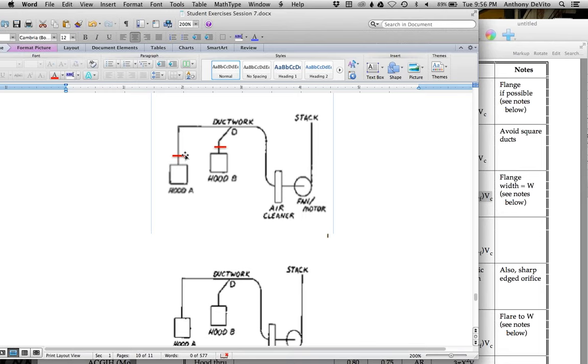They call it a blast gate in these systems. And if it were an air conditioning system like this, it would be a damper, which looks like a butterfly. And you would adjust that to adjust how much air was getting pulled in through that hood, and how much air is getting pulled in through this hood. Anybody ever have air stones in a fish tank? If you got more than one of them, if you open up one too much, the other one doesn't get any air, and you can adjust the valve so you can balance them. That's how these things work. They adjust the blast gates to achieve the velocity that they need in the hood.